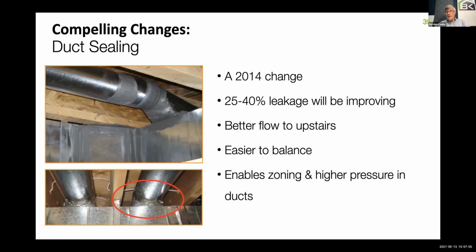Oh, that's significant. Now, here's the issue. It doesn't help you much on the cooling side. And I already said to you, the furnace size doesn't get that much smaller, or sorry, not much cheaper. That is, a 75,000 to a 50,000 isn't a lot of money. But if I can reduce the size of the ductwork, all right, now there's some savings.